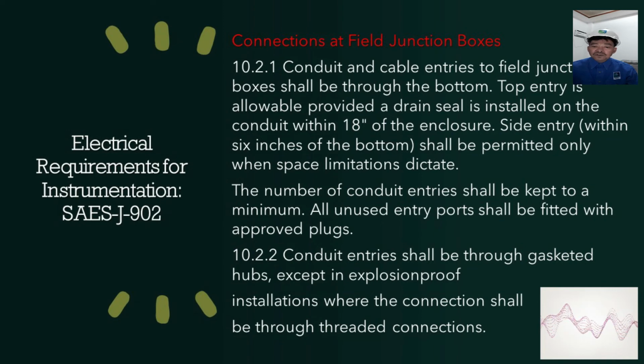Conduit and cable entries to field junction boxes shall be through the bottom. Top entry is allowable provided a drain seal is installed in the conduit within 18 inches of the enclosure. Side entry within 6 inches of the bottom shall be permitted only when space limitation dictates. The number of conduit entries shall be kept to a minimum. All unused entry ports shall be fitted with approved plugs. Conduit entries shall be through gasketed hubs except in explosion-proof installation where the connection shall be through threaded connection. So these are all connections at field junction boxes.